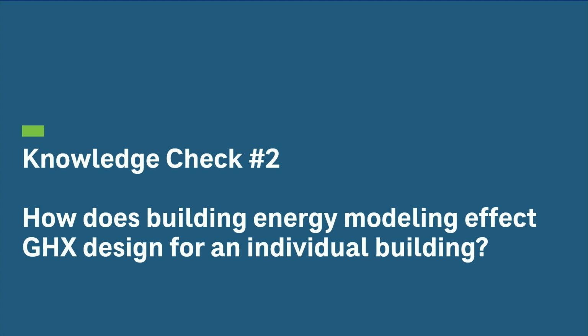I can feel Dr. Kavanaugh channeling through me, so I just need to make a few comments here. You have to remember that this is a model. This helps you get to the right answer. There needs to be some engineering judgment. Keep in mind this is TMY3 data, and with climate change, we're seeing some deviation, at least where I'm practicing engineering. You have to remember this is taking into account the EER and COP of the equipment over a range of temperatures. The thermal properties that you get when you do a thermal properties test are within 10% accuracy of what's really going on. And one thing that this model doesn't take into account is the moisture in the soil.